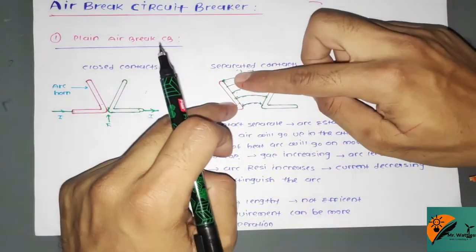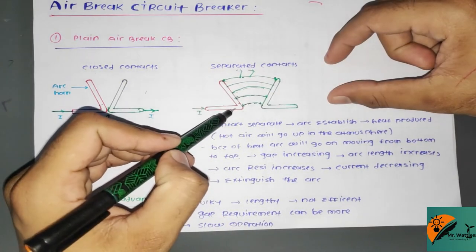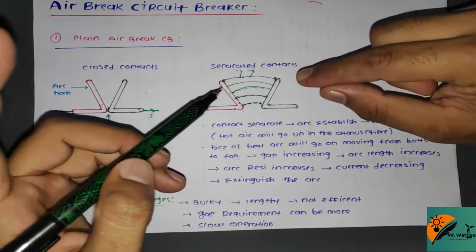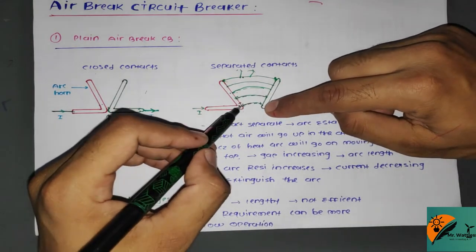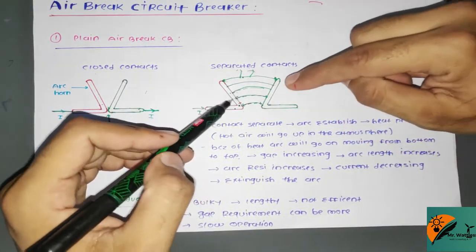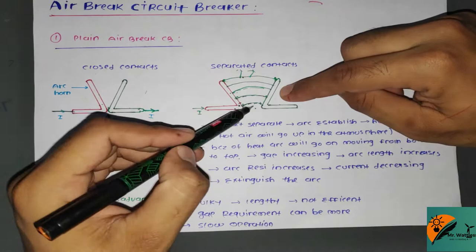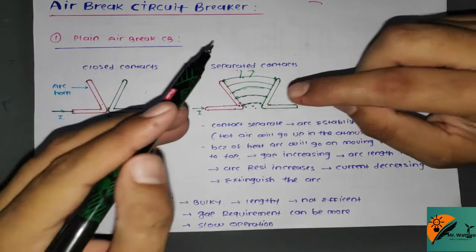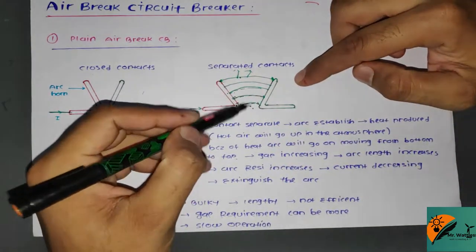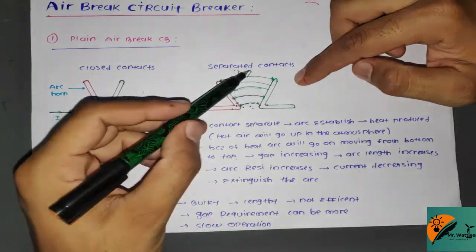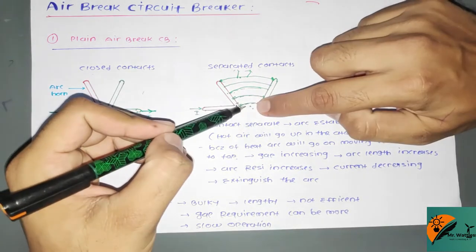When the contacts get separated, an arc is established between them, and heat is produced. We know heat is produced because of the high magnitude of current. Because of this heat, hot gases always rise upward into the atmosphere. So because of heat, the arc will go on moving from bottom to top, and the gap will keep increasing.